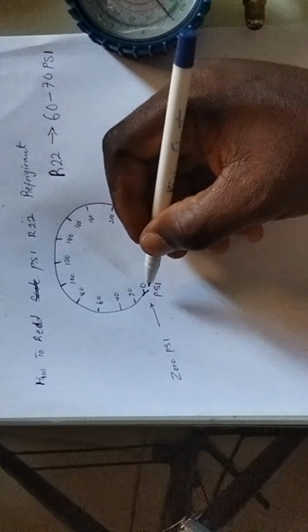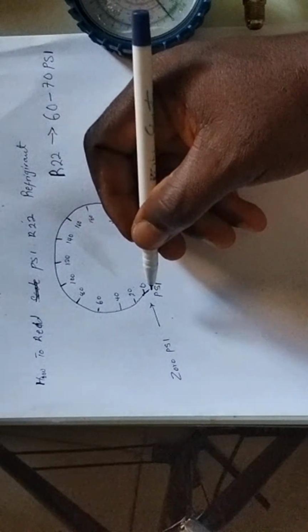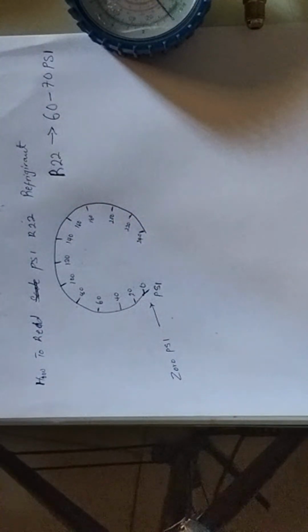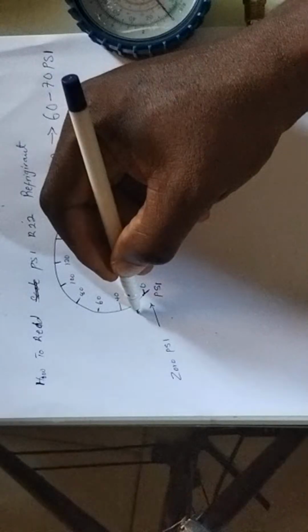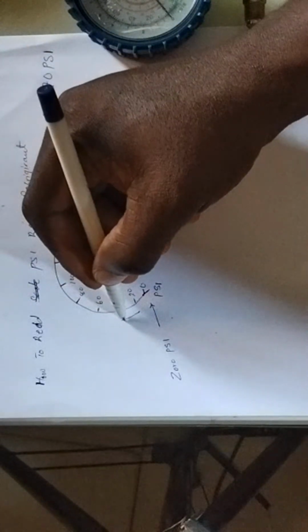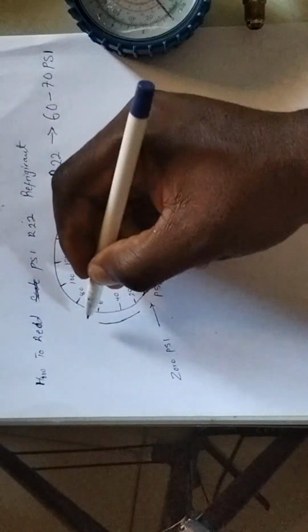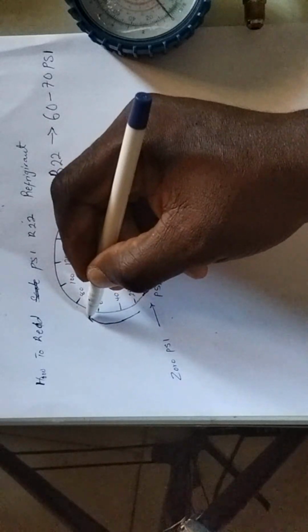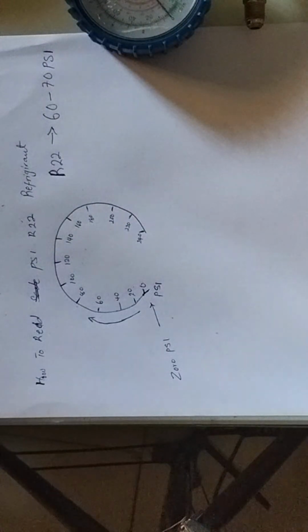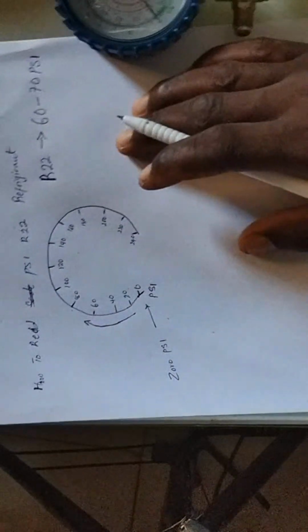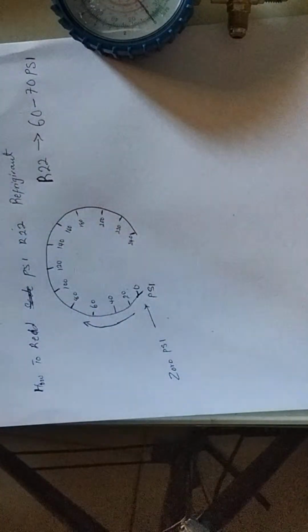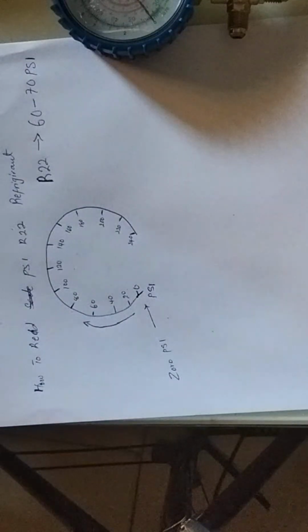You notice it starts from 0 psi. Once you start adding refrigerant on the system, it increases up to 40. You keep adding refrigerant, it increases to 60. If you want to stop at 60, it's not bad. If you can extend to 70 psi, that is also still good. That is also still better. So this is what you have for R22 refrigerant.